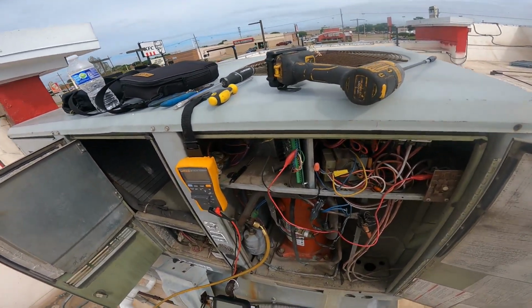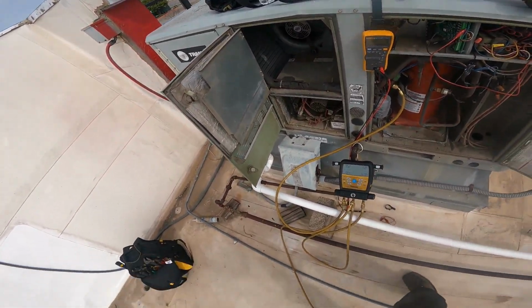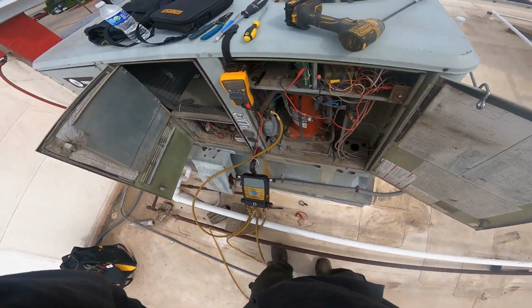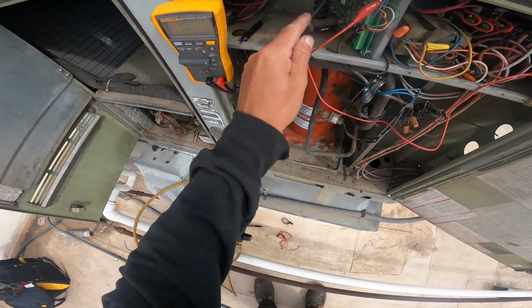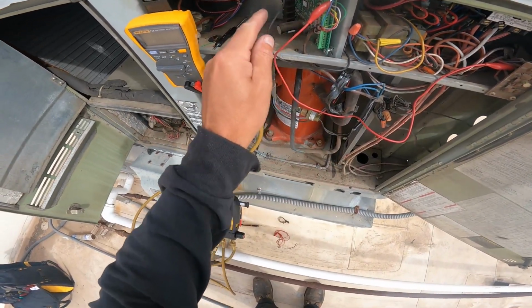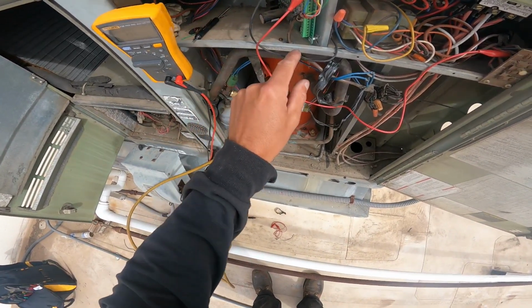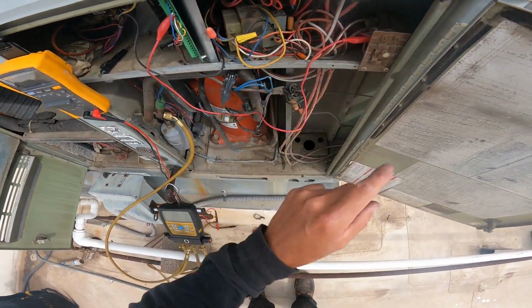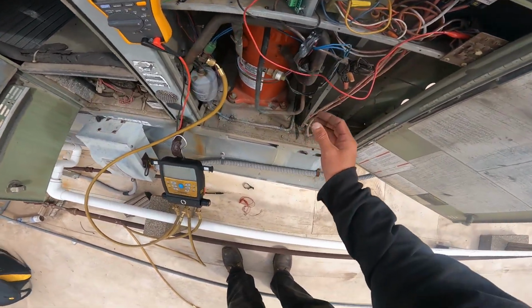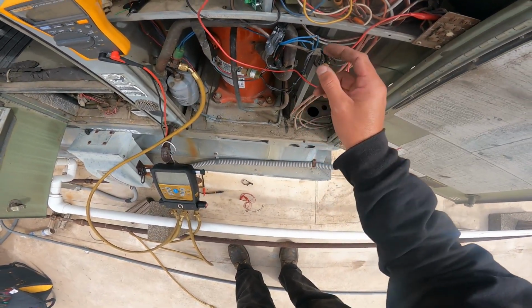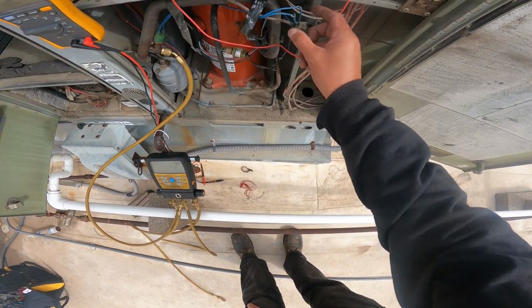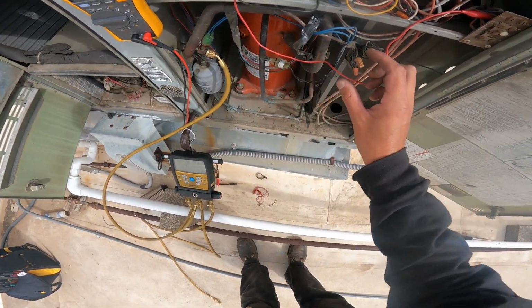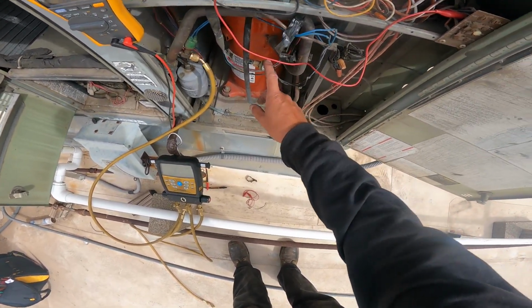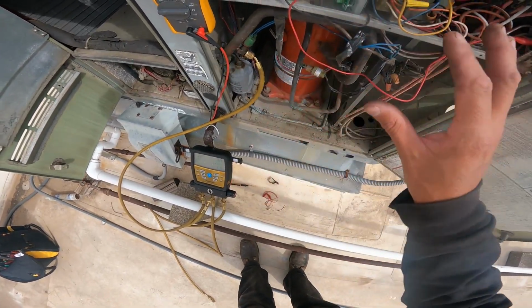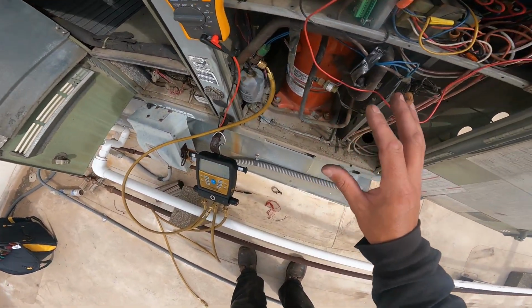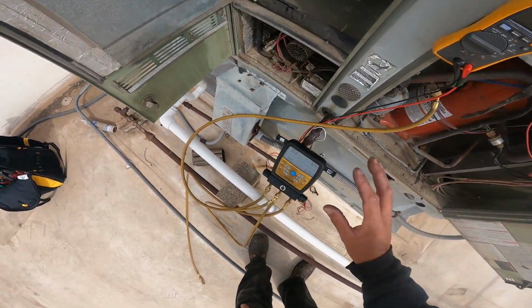I'm gonna test the blower first. I'm leaving this here because if the board is working, it's going to give voltage to this, which is going through the high pressure switch and coming out here, which doesn't really matter because the high pressure switch is bypassed. The low pressure switch was bypassed, but I tested it, it's closed, so low pressure is good. The high pressure is stuck open. I'm going to leave that bypassed. We want to find out why, so I'm not going to leave it bypassed when I leave here, but it is bypassed for now.